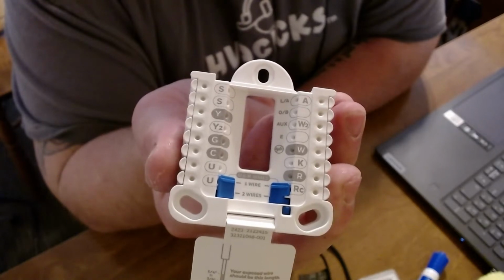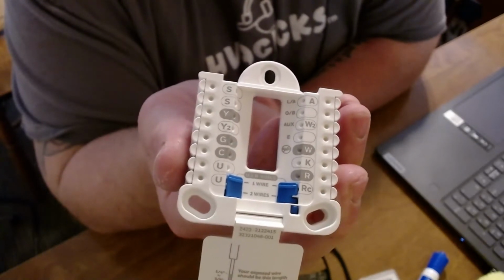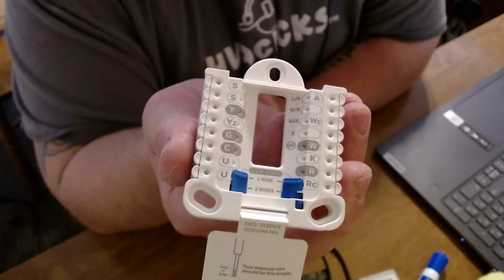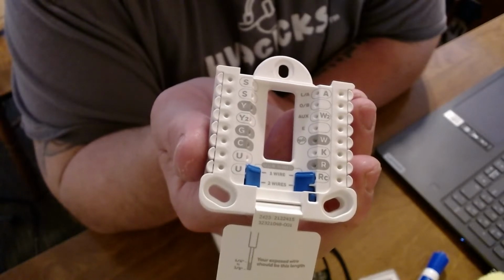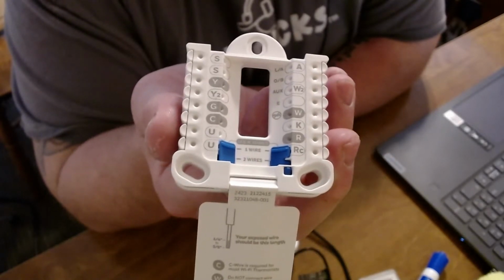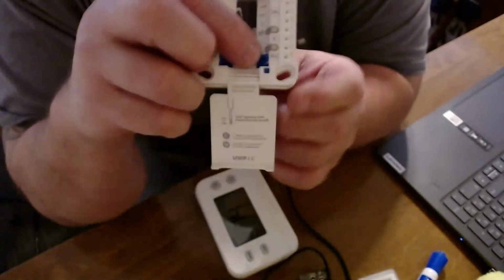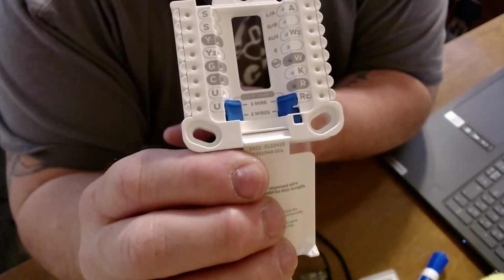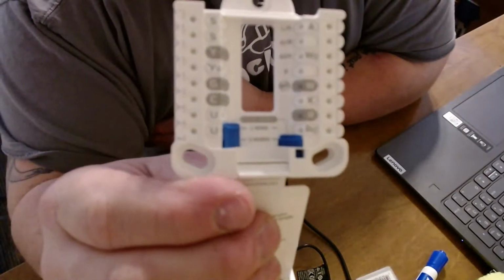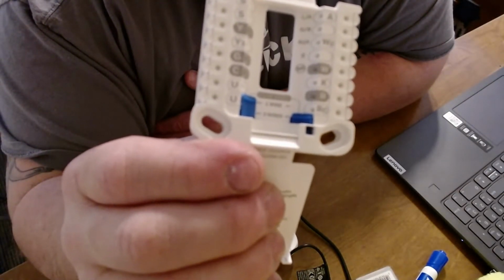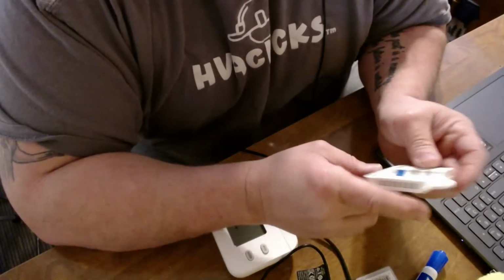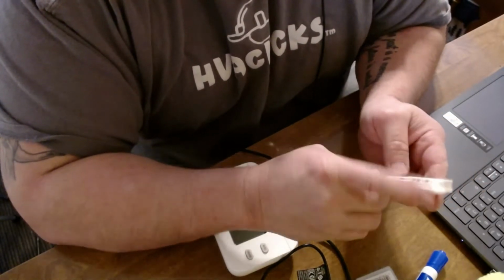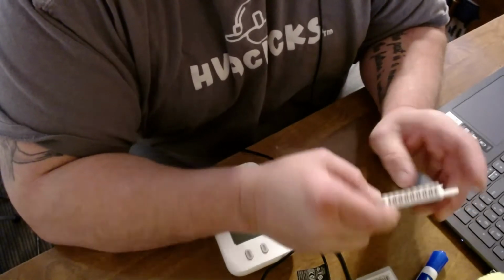Now, as you can see, this is our wiring. So we have Y1, Y2, W1, W2, right? So you would wire this up, W for W1, W2 for second stage. If you notice right there on the R section, on this side, it says 1 wire or 2 wire. You see how it's pushed up where it says 1 wire? If I were to drop this down and set it for 2 wire, now look, the R and RC terminals are both exposed. So you can use this thermostat for 2 different type systems, one for cooling, one for heating. And if you want to use the U wires, you can drop that down. So you can use UU, and you also have SS.